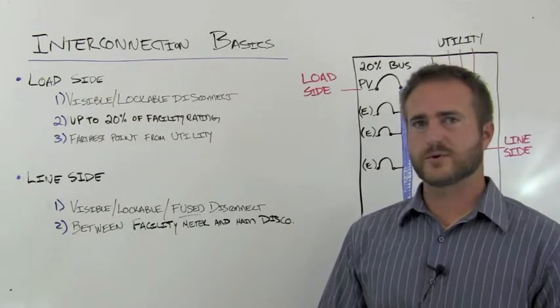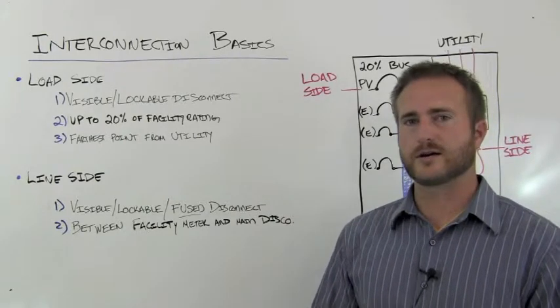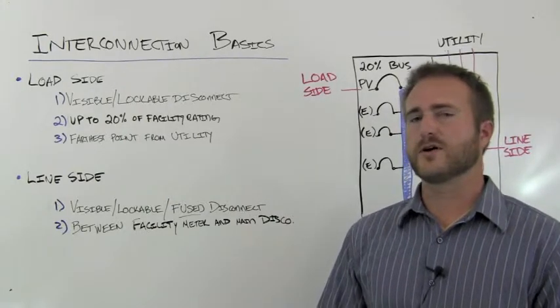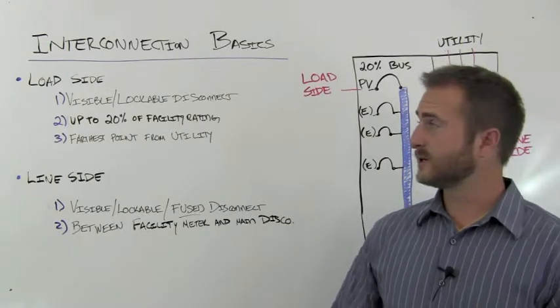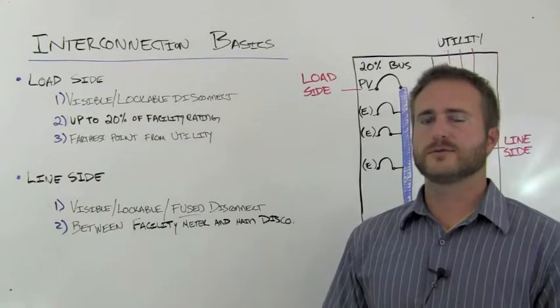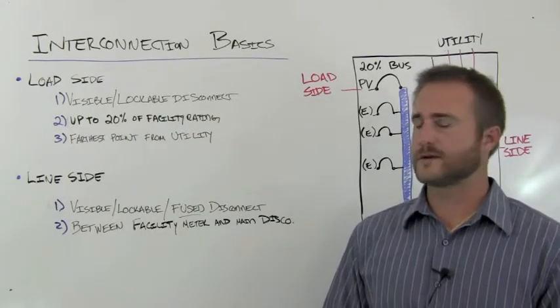What that means is 100% of your power is going to be coming from the utility—that's usually the rating of your gear. And 20% you can overload that rating by adding additional PV. But you're limited to point number three: you need to install your PV at a point farthest away from your utility coming into that switchgear.